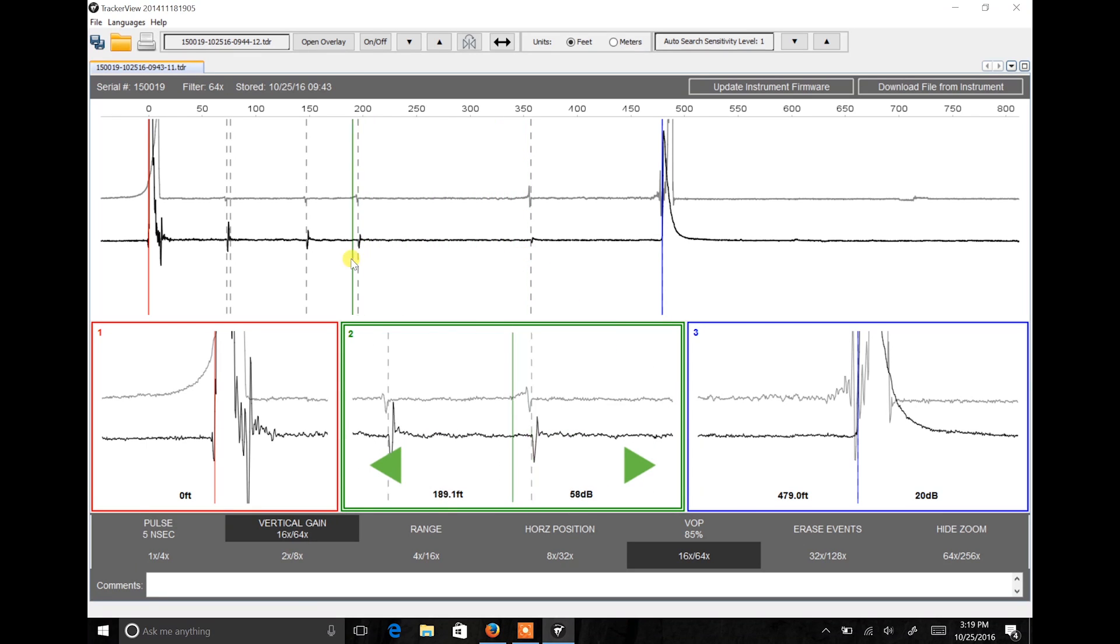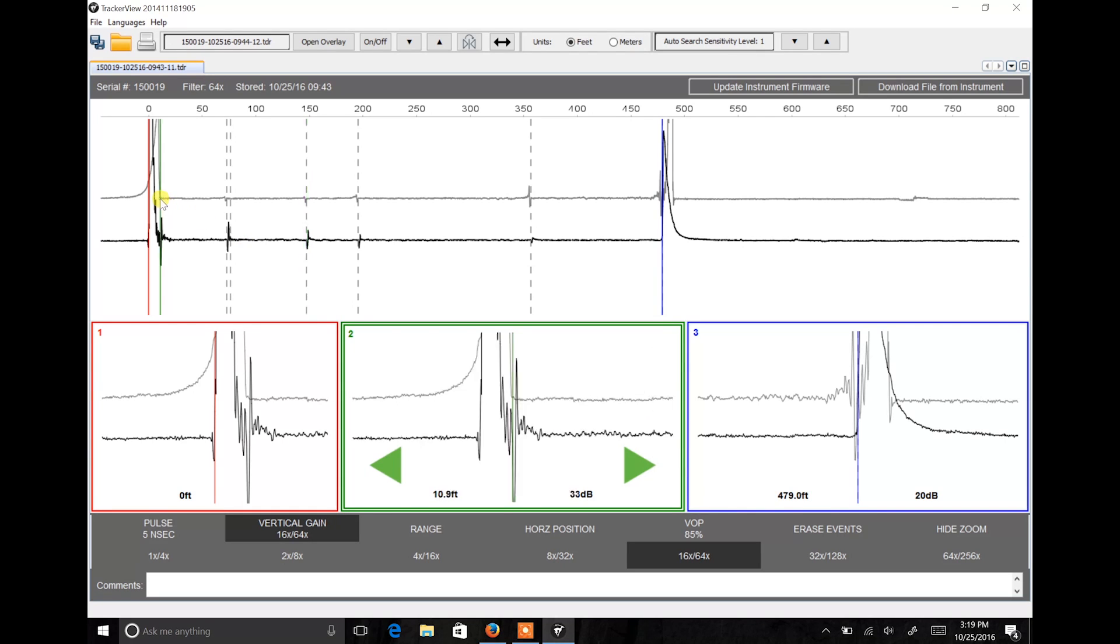You may notice that the end of cable on my overlay does not align with the outgoing pulse of my primary waveform. This is due to the fact that we used a 10-foot jumper to connect from the TDR to the cable under test.